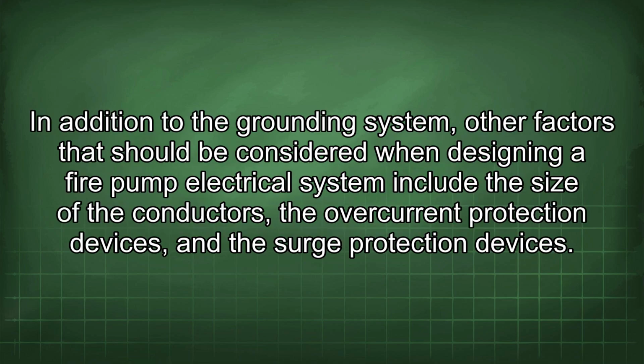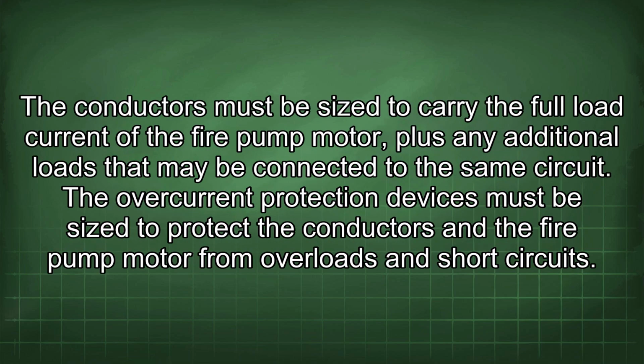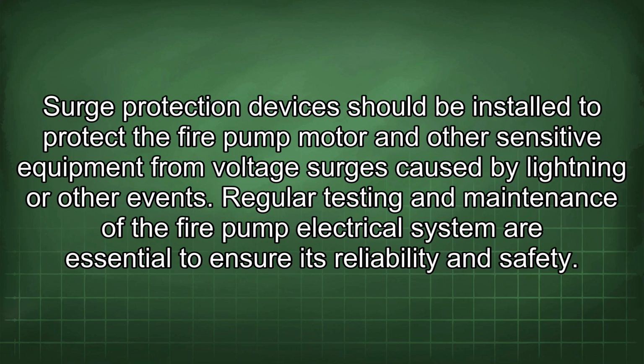In addition to the grounding system, other factors that should be considered when designing a fire pump electrical system include the size of the conductors, the overcurrent protection devices, and the surge protection devices. The conductors must be sized to carry the full load current of the fire pump motor, plus any additional loads that may be connected to the same circuit. The overcurrent protection devices must be sized to protect the conductors and the fire pump motor from overloads and short circuits. Surge protection devices should be installed to protect the fire pump motor and other sensitive equipment from voltage surges caused by lightning or other events.